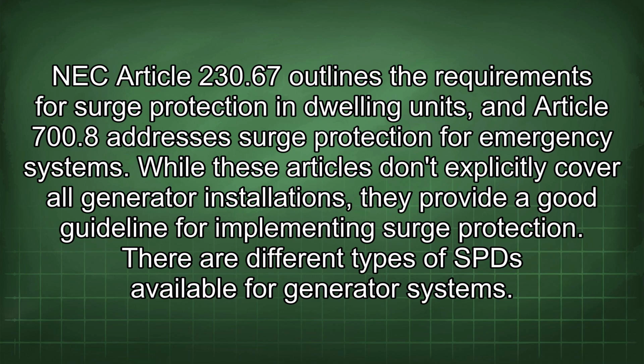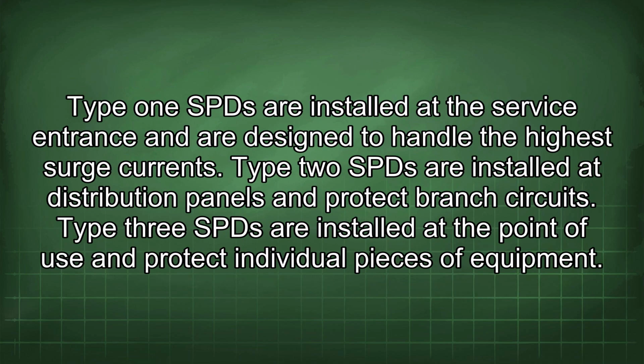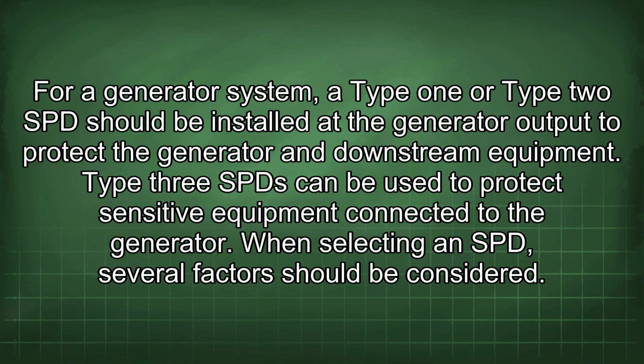There are different types of SPD available for generator systems. Type 1 SPD are installed at the service entrance and are designed to handle the highest surge currents. Type 2 SPD are installed at distribution panels and protect branch circuits. Type 3 SPD are installed at the point of use and protect individual pieces of equipment. For a generator system, a Type 1 or Type 2 SPD should be installed at the generator output to protect the generator and downstream equipment. Type 3 SPD can be used to protect sensitive equipment connected to the generator.